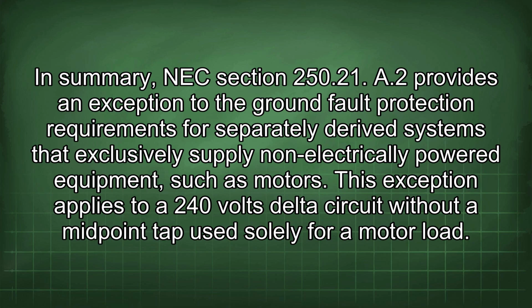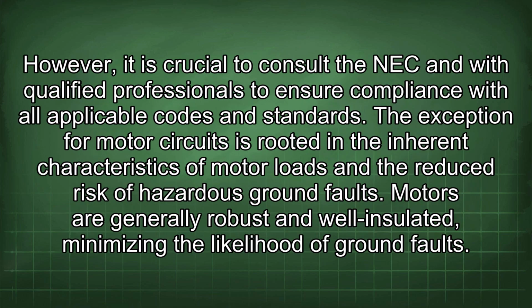In summary, NEC section 250.21 A2 provides an exception to the ground fault protection requirements for separately derived systems that exclusively supply non-electrically powered equipment, such as motors. This exception applies to a 240 volts delta circuit without a midpoint tap used solely for a motor load. However, it is crucial to consult the NEC and qualified professionals to ensure compliance with all applicable codes and standards. The exception for motor circuits is rooted in the inherent characteristics of motor loads and the reduced risk of hazardous ground faults.